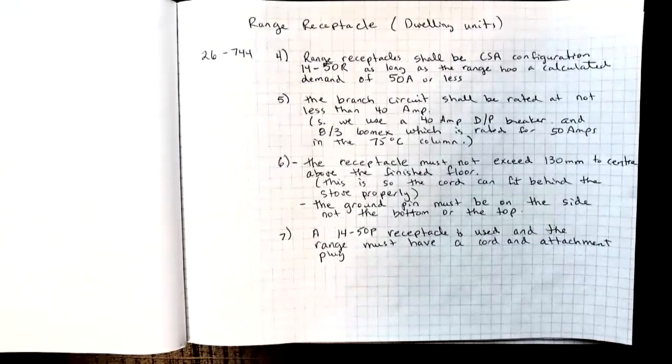Sub-rule 6: the receptacle must not exceed 130 millimeters to the center when measured above the finished floor. This is so that the cord can fit behind the stove properly.